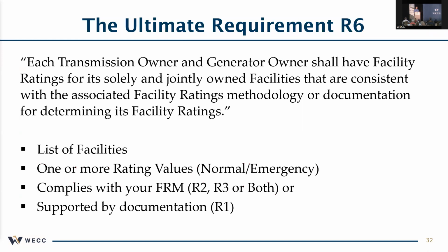So you get all that together and you get to requirement 6. And by the way, I'm not going to talk about requirement 8. That's just communicating the ratings as requested. You don't really see too many issues with that. But you've got to use these methodologies to come up with your facility rating. And what we look for is listed facilities, one or more rating values, normal, emergency. At this time, we have a lot of companies that rate them the same. I think there'll be less of that once they fully incorporate FERC 881, but maybe not for a generator.